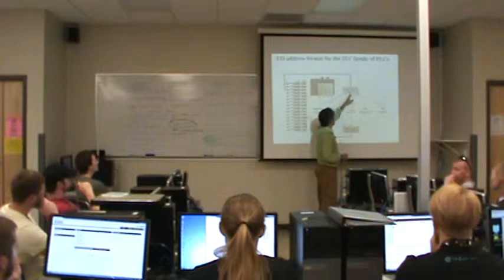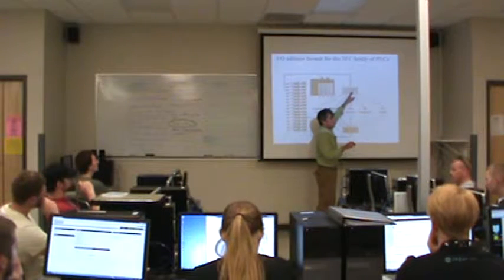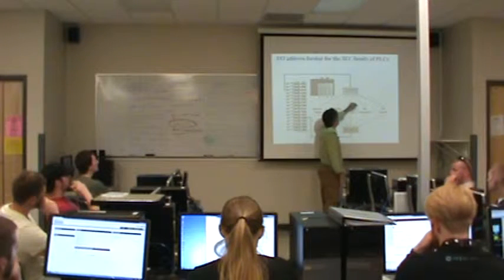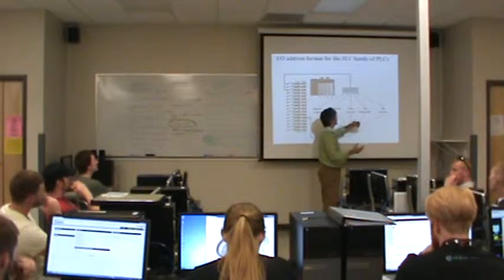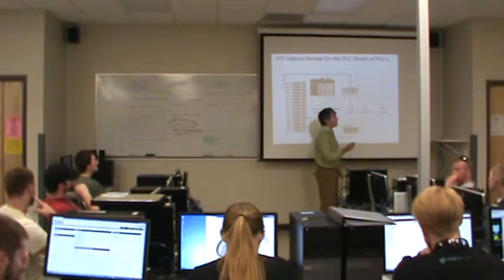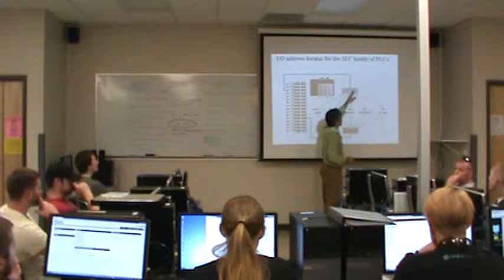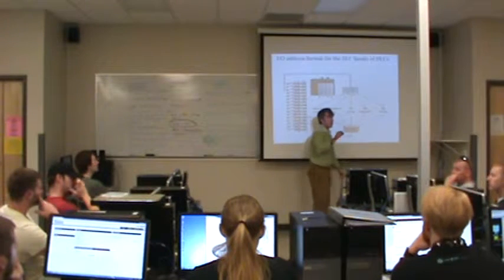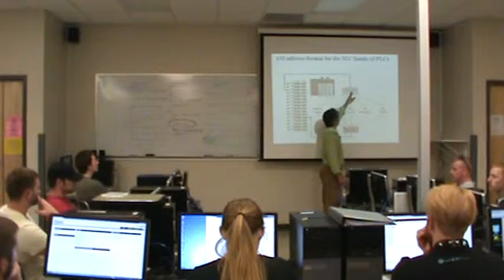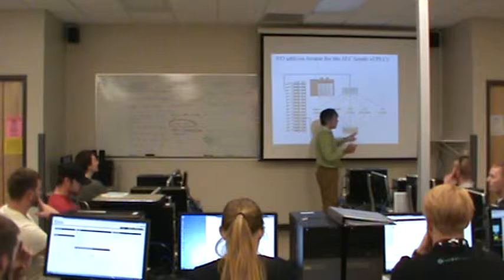This delimiter here, the separator, tells you that what comes next is essentially a word. It's a whole bunch of data. So this is word 1, or it can be a slot number depending on the particular syntax. And then the slash tells you that what comes next is a bit. So this colon tells you that the thing following is a word, the slash tells you that the thing following is a bit of that word. So this is input 1, bit 2. This is output word 2, bit 11.